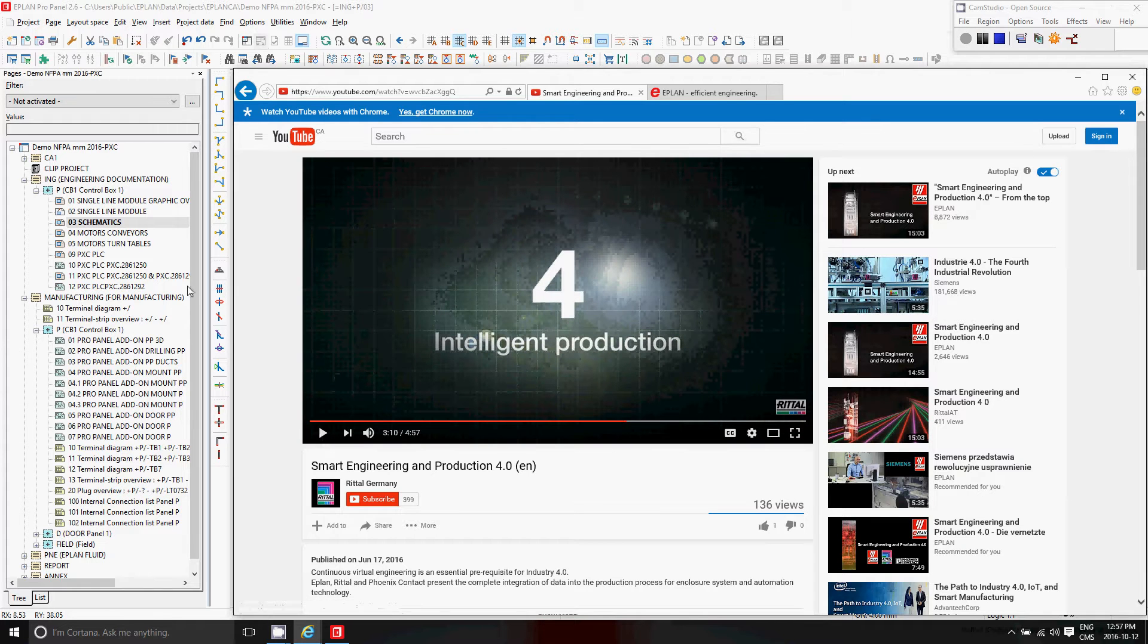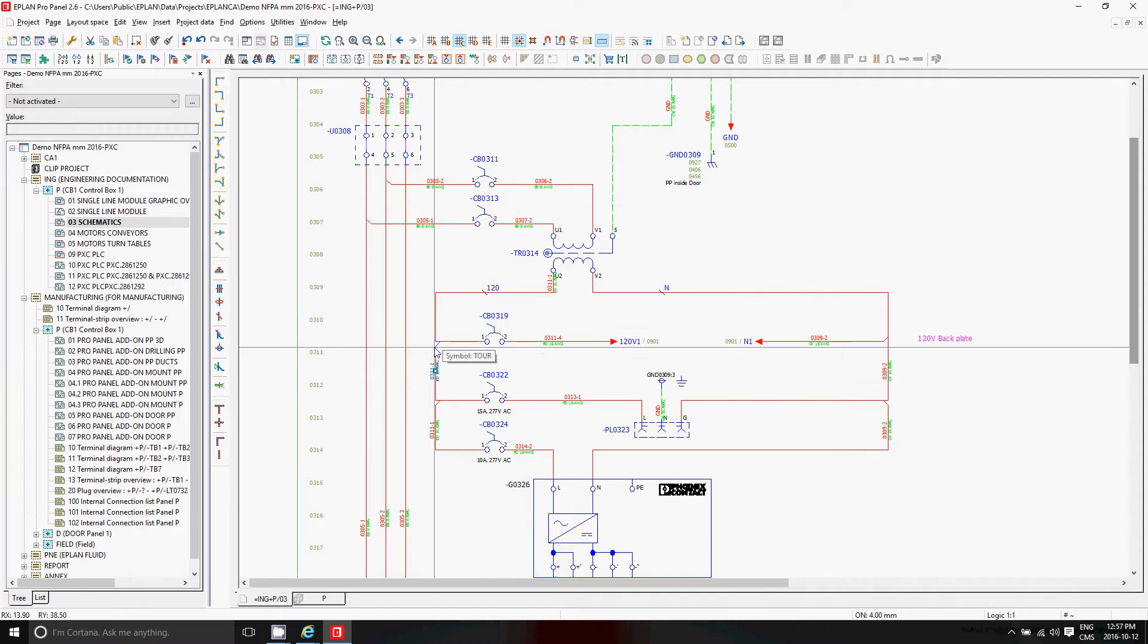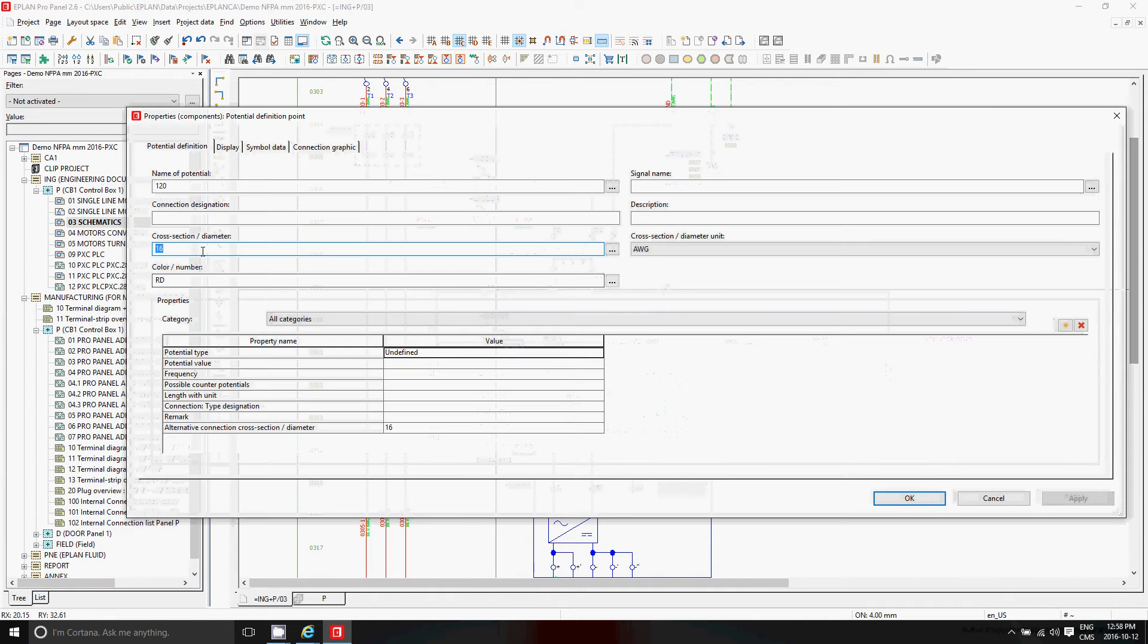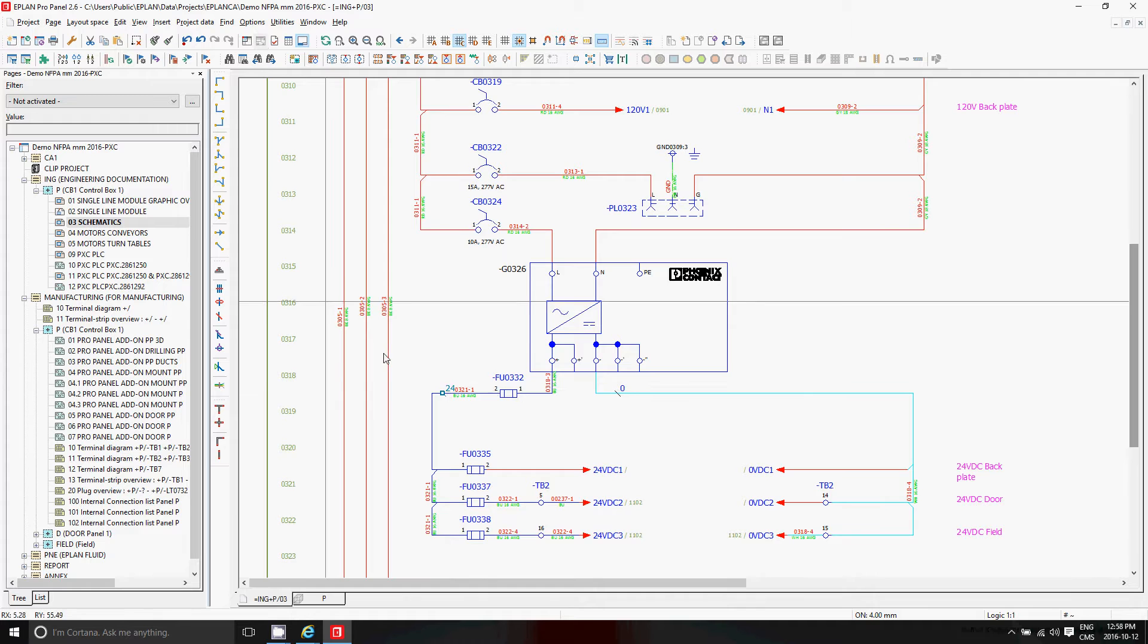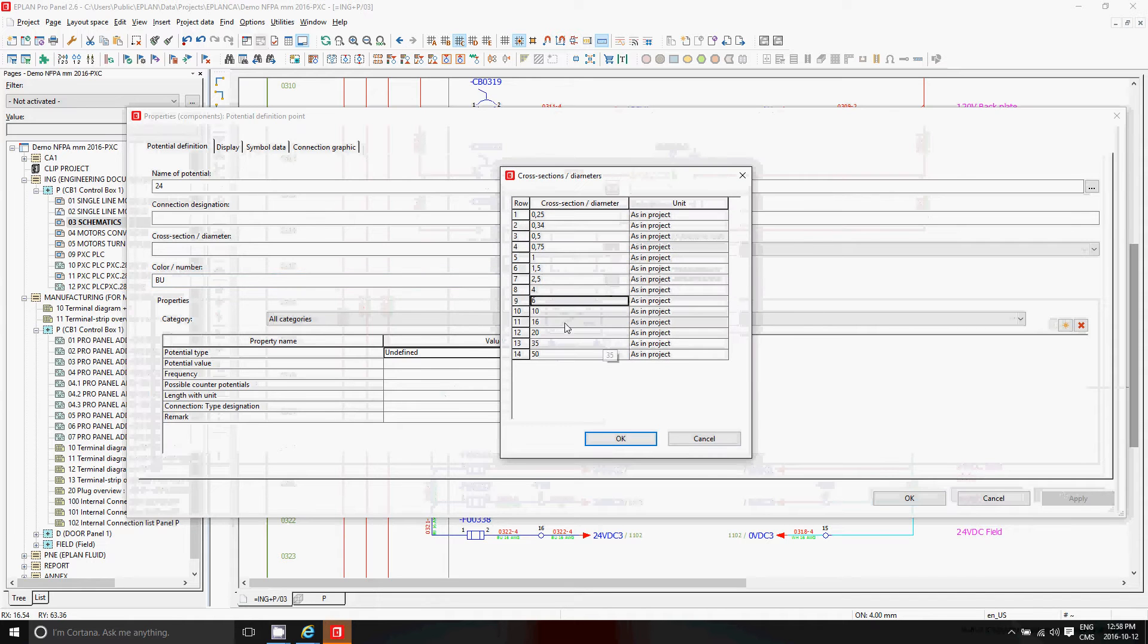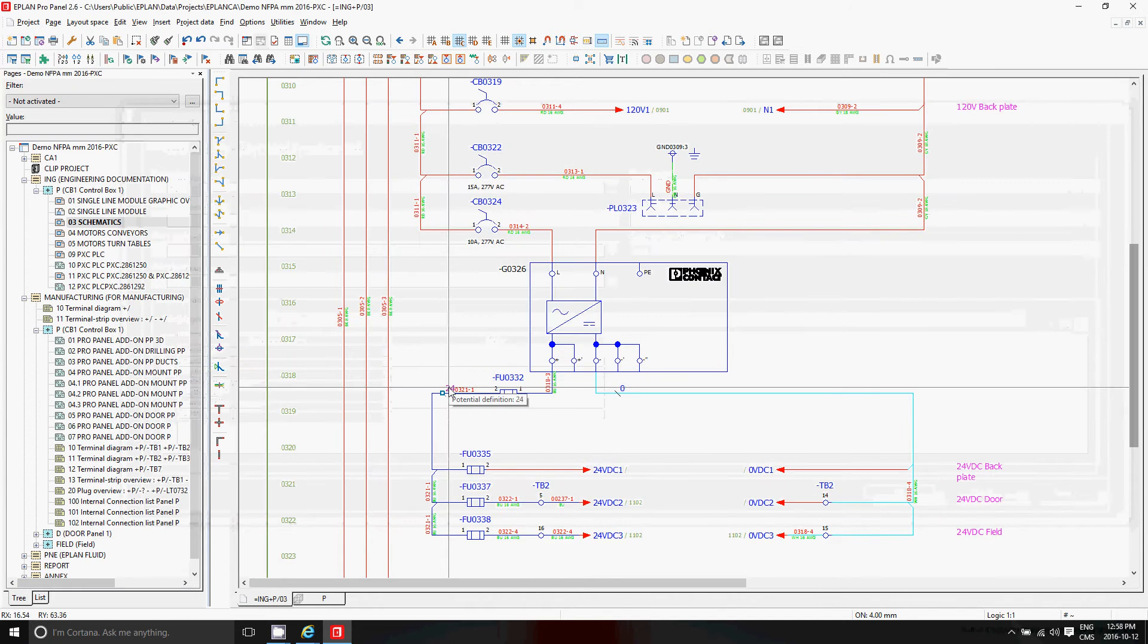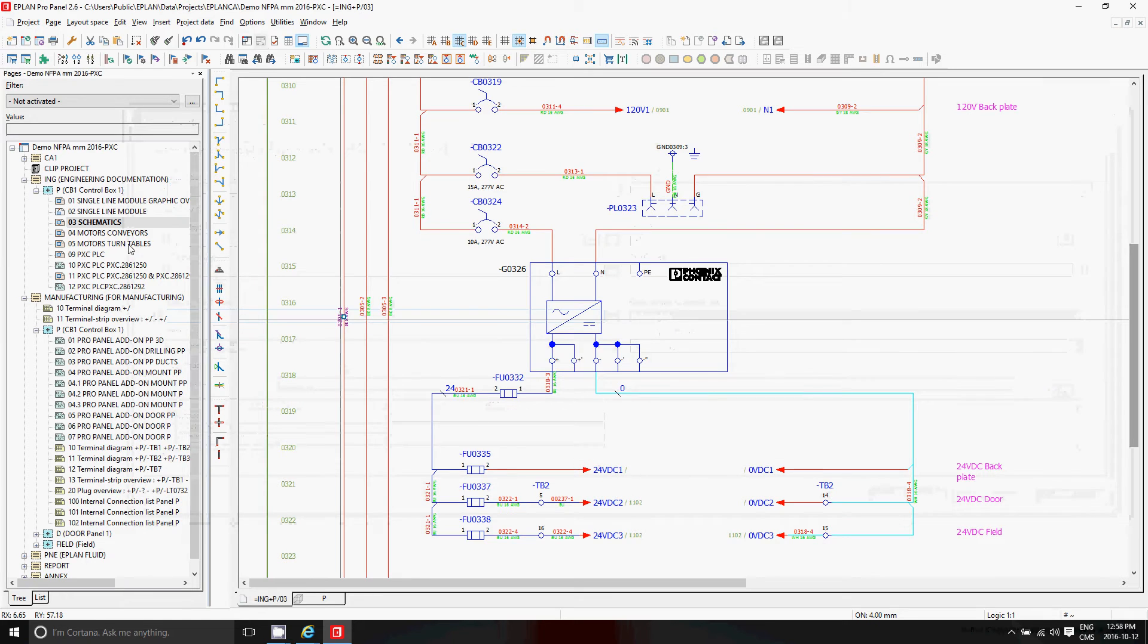So, on the ePlan side, we know that we have wires that are generated here from the correct T-node that goes from one device to another. And when you actually look at the potential, you can see that for the 120V, we're generating some red wires. If I move down here to the 24VDC, the 24VDC is recognized here with a different color, which is the blue wire. I can associate here a specific value, let's say 20 gauge American wire gauge, to be the size. I can resize it, and this gives me actually the sizing of every single wire, or I can do it individually. I can double click on one specific wire and specify what I want.